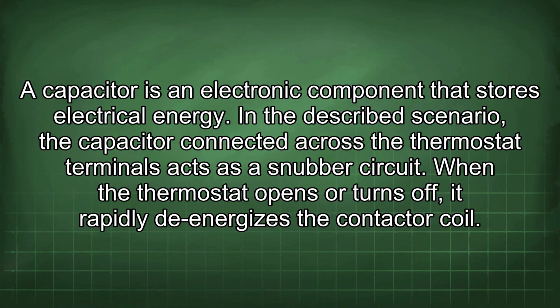A capacitor is an electronic component that stores electrical energy. In the described scenario, the capacitor connected across the thermostat terminals acts as the snubber circuit. When the thermostat opens or turns off, it rapidly de-energizes the contactor coil.